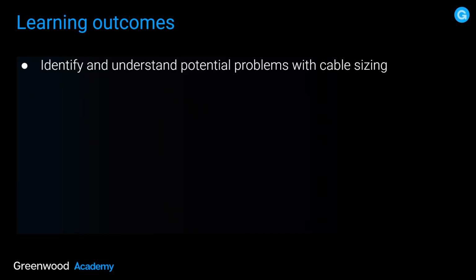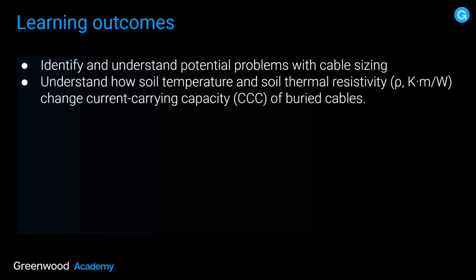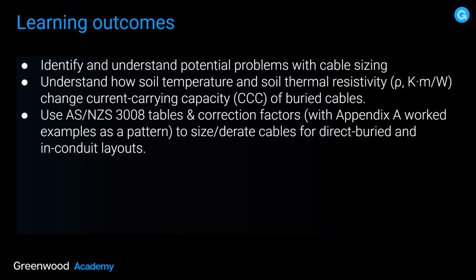We're going to identify and understand potential problems with cable sizing. We're going to understand how soil temperature and soil thermal resistivity changes current carrying capacity, the CCC, of buried cables. We're going to use AS/NZS 3008 tables and correction factors with Appendix A worked examples as a pattern to size and derate cables for direct buried, but we're not going to really look at in-conduit layouts. And we're going to develop a methodical step-by-step process.